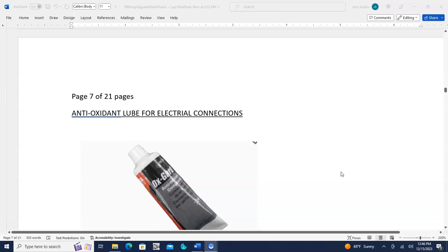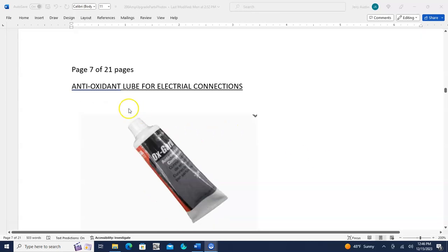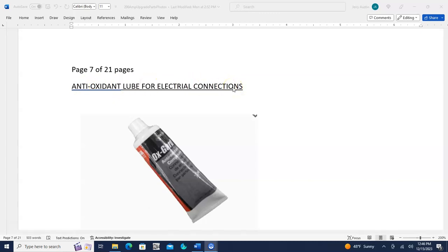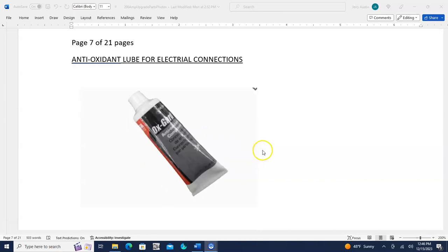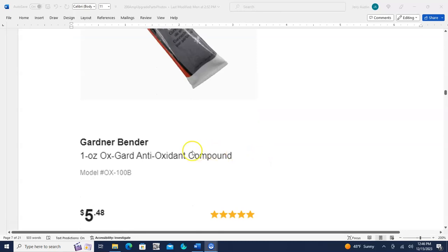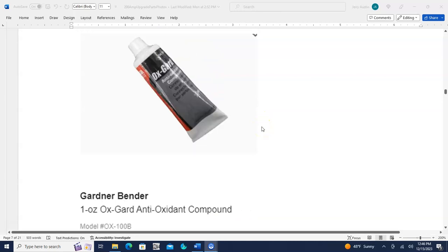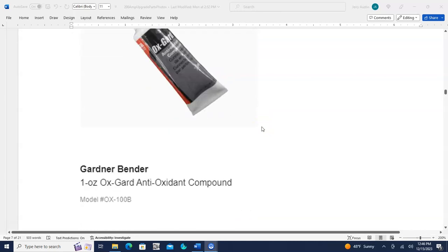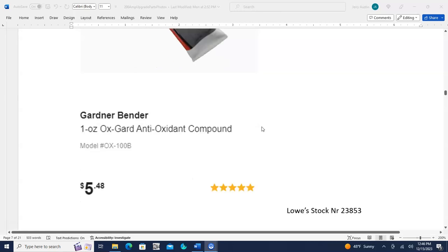This antioxidant, you need to put this on the wires coming in from the main power into the top of the meter base. You need to lube them down real good with this. They're aluminum wires, and also any other connection made with those big aluminum wires needs to be lubed down really, really good. That prevents oxidation from taking place - if oxidation does take place, the connections get loose, and the thing won't work anymore.